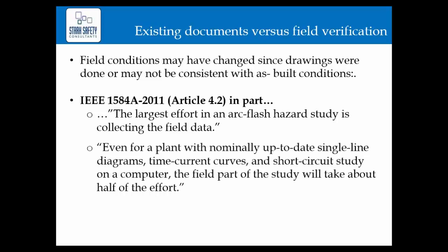Even if we have an up-to-date one-line diagram in place for the time current curve and short circuit study that may be in the computer, the field part of the study could take as much as half the amount of time to do the overall study. It's very important that we understand we have to go get the field conditions.